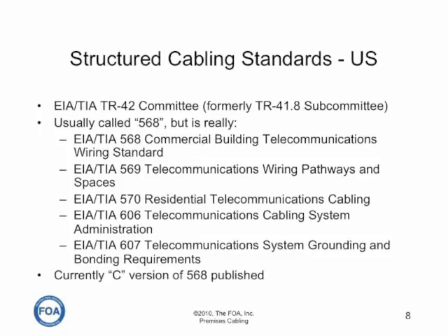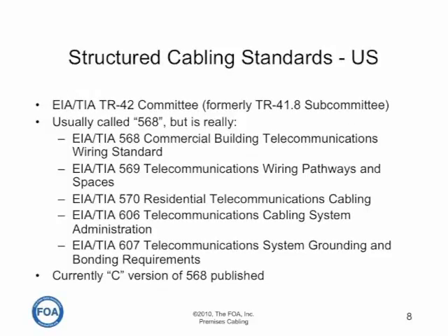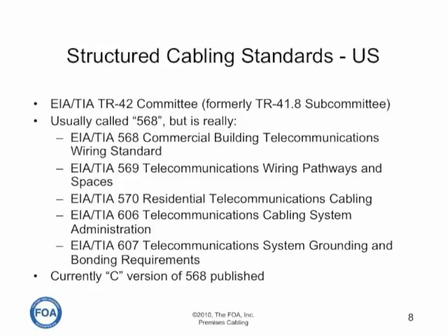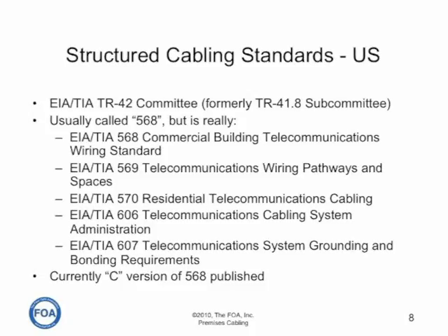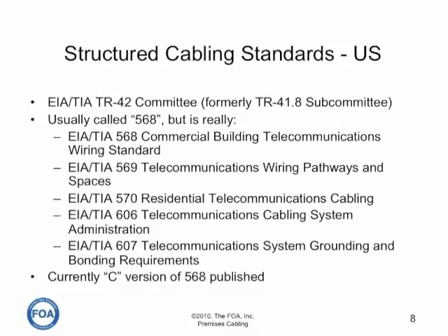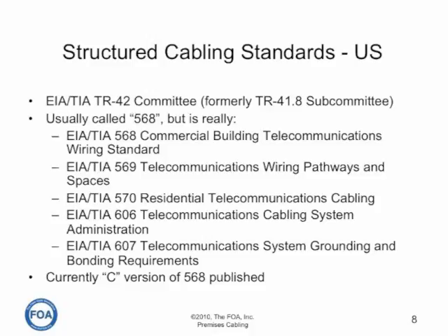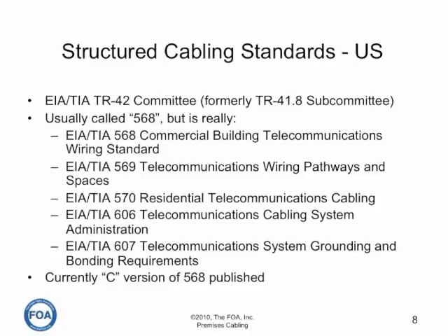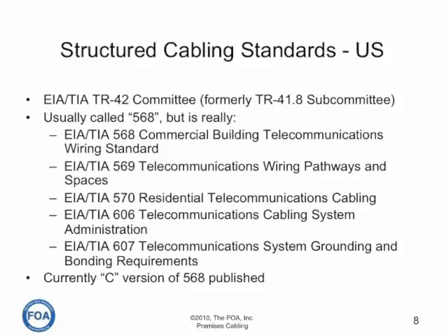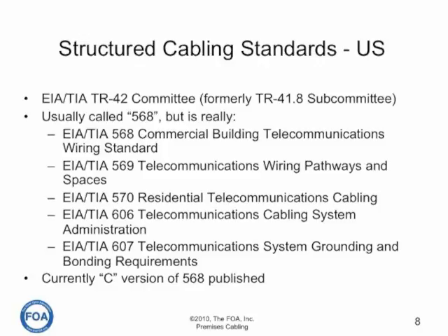In the US, structured cabling is based on work by the EIA-TIA-TR42 committee. It's usually called the 568 standards, but it's really the 568 standard for building telecommunications standards, 569 for wiring pathways and spaces, 570 for residential telecommunications, 606 for administration, and 607 for grounding and bonding requirements. At the current time, 568 is in its C revision, but it's being revised continuously, so you really don't know exactly what each standard is in the latest version unless you're a manufacturer attending the standards committees.